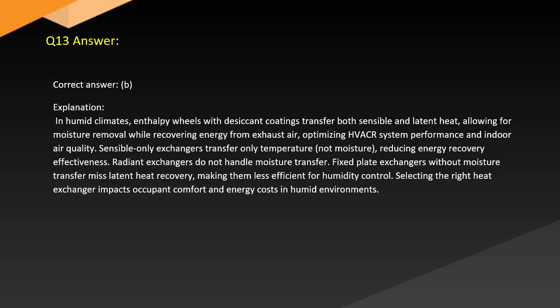Answer. Correct answer. B. Explanation. In humid climates, enthalpy wheels with desiccant coatings transfer both sensible and latent heat, allowing for moisture removal while recovering energy from exhaust air, optimizing HVACR system performance and indoor air quality. Sensible-only exchangers transfer only temperature, not moisture, reducing energy recovery effectiveness. Radiant exchangers do not handle moisture transfer. Fixed plate exchangers without moisture transfer miss latent heat recovery, making them less efficient for humidity control. Selecting the right heat exchanger impacts occupant comfort and energy costs in humid environments.